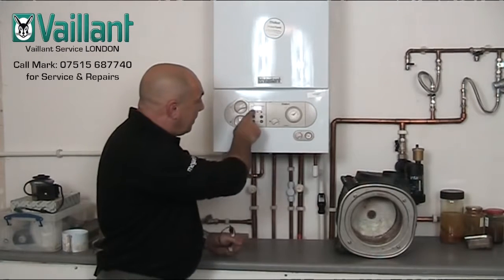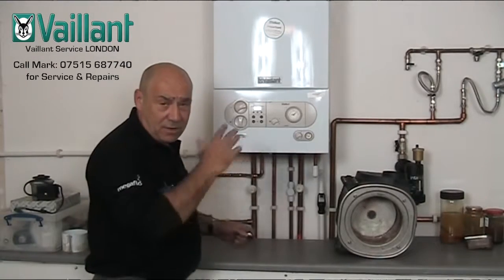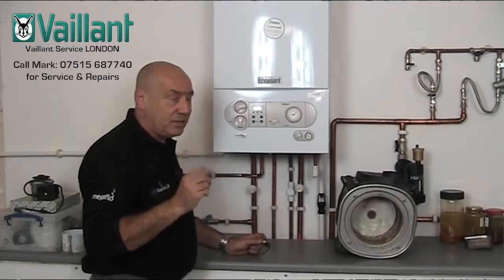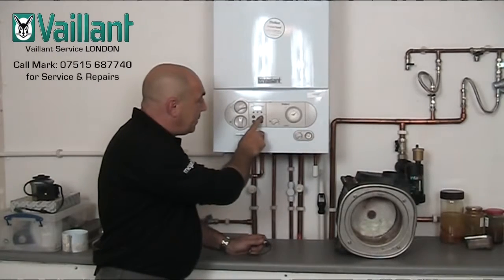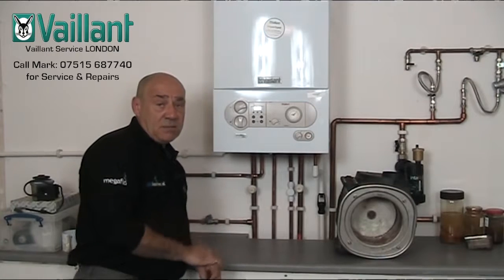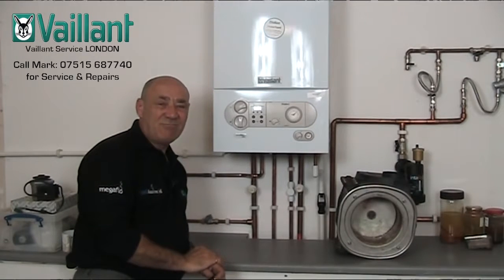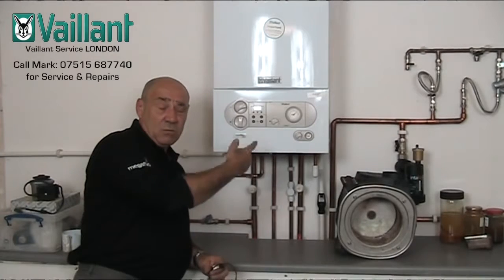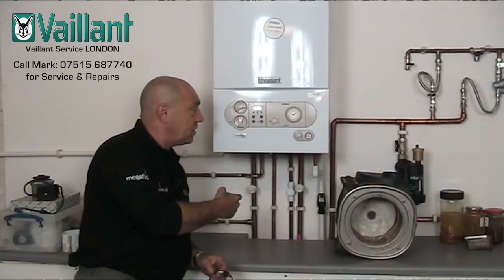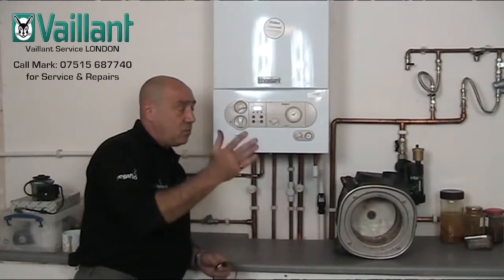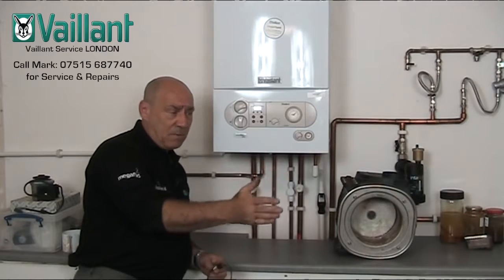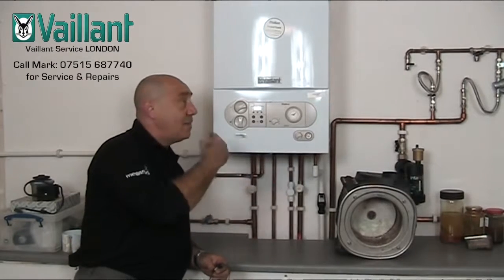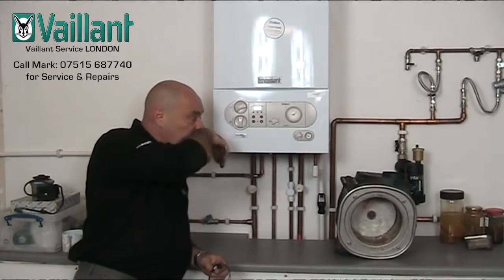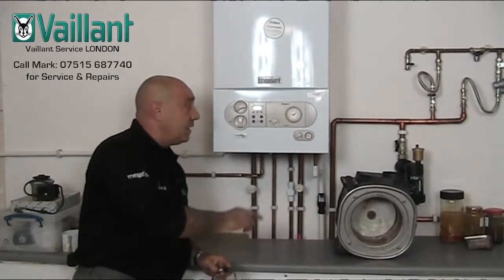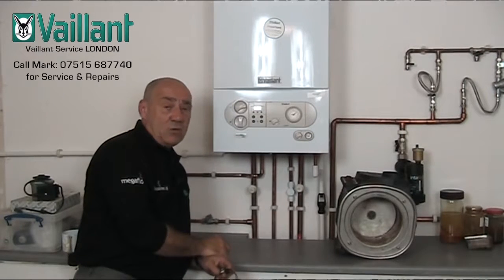The display will then flash up P.0. Now there are other test programs you can use, but P0 is the one that we're interested in because that's the purge program. If I then just push the i button, the boiler will now start the test program, and I can go and have a cup of tea, because that will run the domestic hot water circuit and the heating circuit for the main heat exchanger for a predetermined period of time. It will continuously move the diverter valve from one position to the other to ensure that the whole system, the boiler and the plate heat exchanger circuit, has all been purged of air. And once that's completed, the P0 will stop flashing, it will revert back to normal display, and you can then turn the boiler on and start using and burning gas.